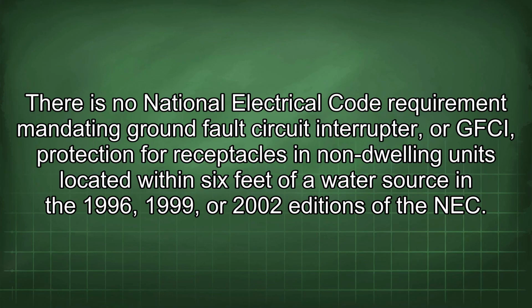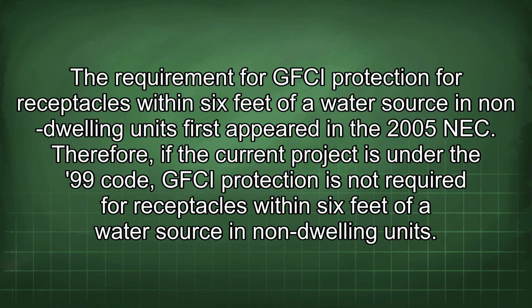There is no National Electrical Code requirement mandating ground fault circuit interrupter, or GFCI, protection for receptacles in non-dwelling units located within 6 feet of a water source in the 1996, 1999, or 2002 editions of the NEC. The requirement for GFCI protection for receptacles within 6 feet of a water source in non-dwelling units first appeared in the 2005 NEC. Therefore, if the current project is under the 99 code, GFCI protection is not required for receptacles within 6 feet of a water source in non-dwelling units.